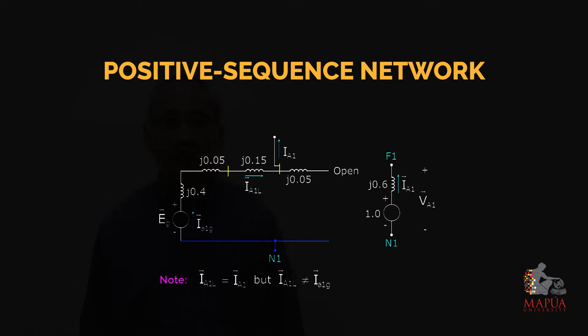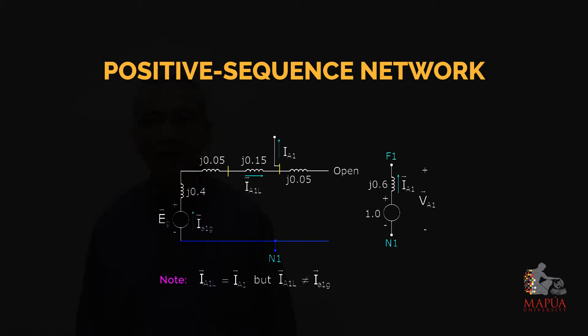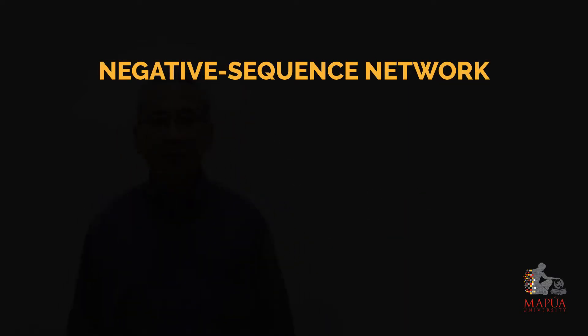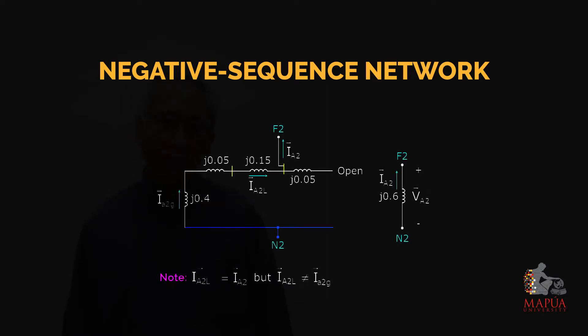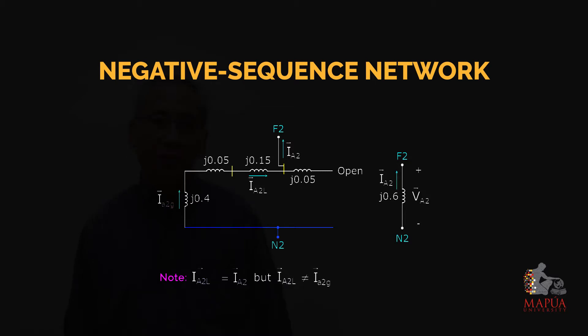Note that in the positive sequence network, the current IA in the transmission line is not equal to the generator current IA flowing through the generator, but it will be equal to the current flowing to the faulted point F1. For the negative sequence network, the connection pattern is similar to the positive sequence network but without the sources. We indicate the negative sequence reactances of all components and determine its Thevenin equivalent. The current flowing through the transmission line I2L is equal to the current flowing through the faulted point IA2, but not equal to the generator current I2G.